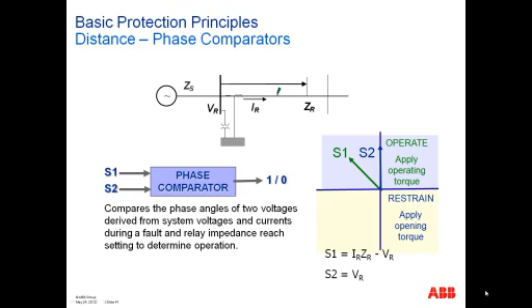Now, the basic principle of a phase comparator is that you have two quantities here. I show S1 and S2, and you're going to compare those angles. What I'm showing here is that with S2 in the given direction in the diagram, if S1 is within 90 degrees leading or lagging of S2, you're always generating operating torque, and you'll eventually get an operation. If it's lagging or leading by more than 90 degrees, you'll get a restraining torque.